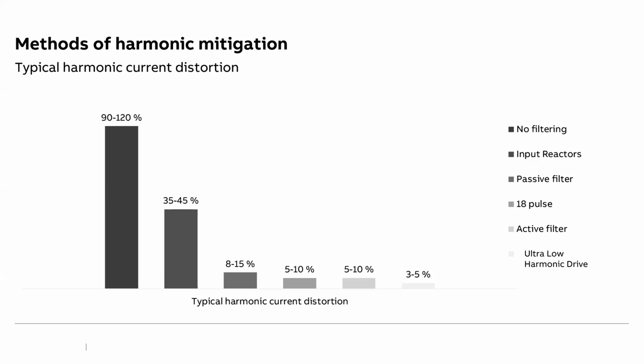So all the drives have basically pulses. If it's a 6 diode, as we had seen in the construction, there's a diode bridge. So we have a 6 pulse drive. The drive which we use in HVAC is always a 6 pulse drive. There are 12 pulse, 18 pulse, 24 pulse drives available. However, this is not applicable to us. For us, it is a basic reactor, the DCR or the choke.